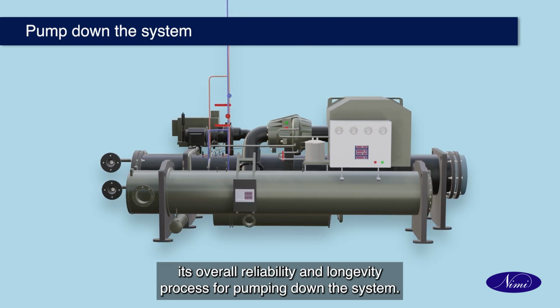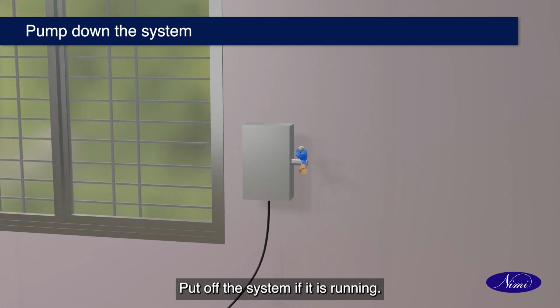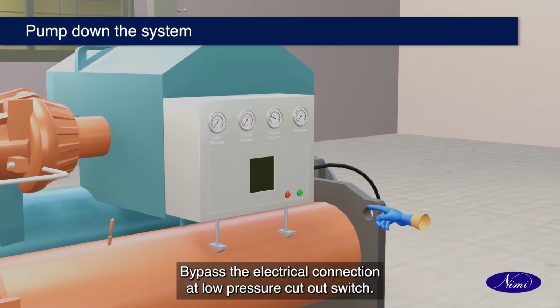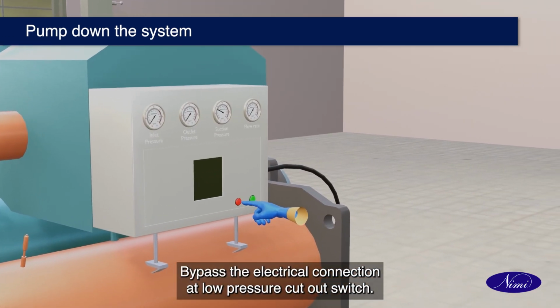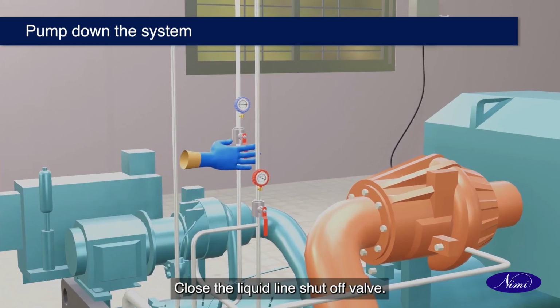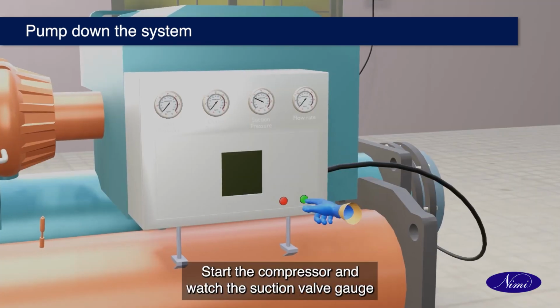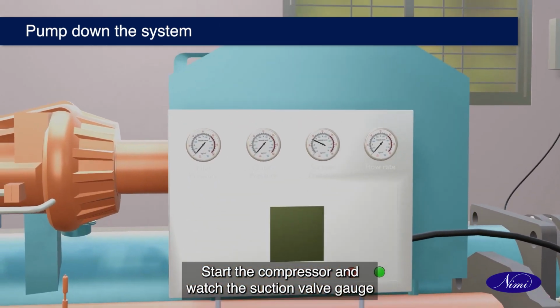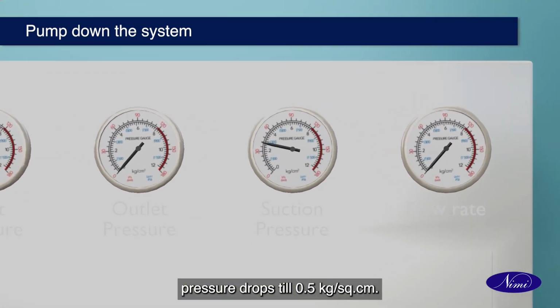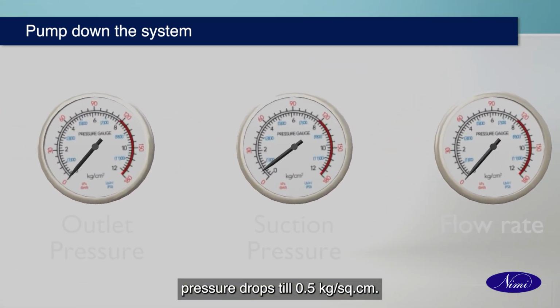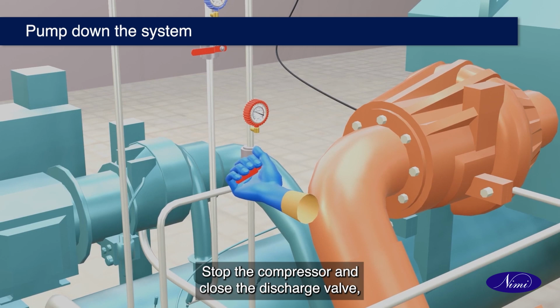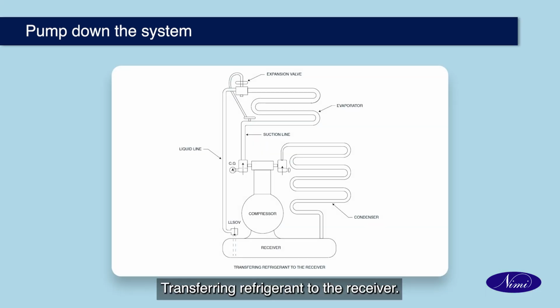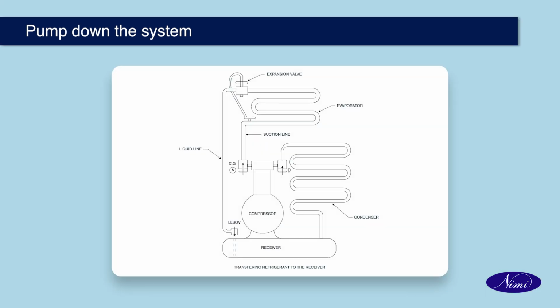Process for pumping down the system. Put off the system if it is running. Bypass the electrical connection at the low pressure cutout switch. Close the liquid line shut-off valve. Start the compressor and watch the suction gauge pressure drop till 0.5 kg per square centimeter. Stop the compressor and close the discharge valve, transferring refrigerant to the receiver.